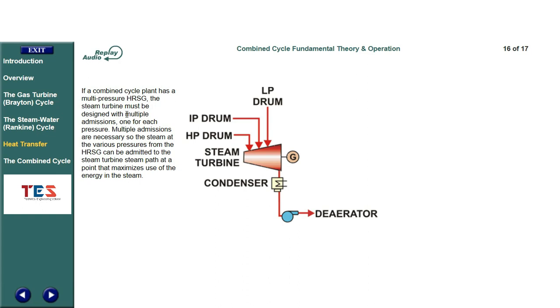If a combined cycle plant has a multi-pressure HRSG, the steam turbine must be designed with multiple admissions — one for each pressure. Multiple admissions are necessary so the steam at various pressures from the HRSG can be admitted to the steam turbine steam path at a point that maximizes use of the energy in the steam.